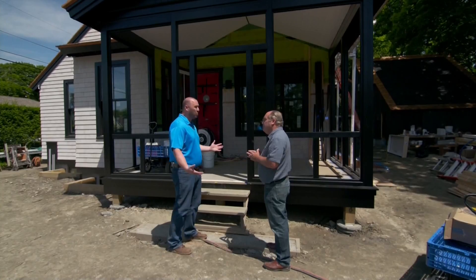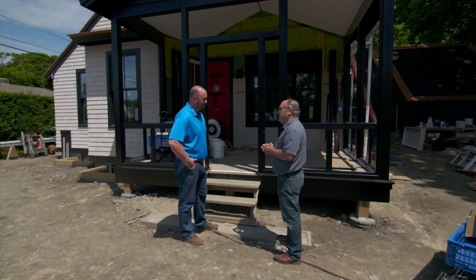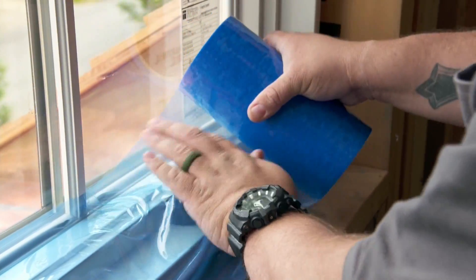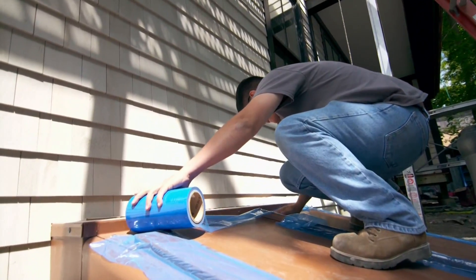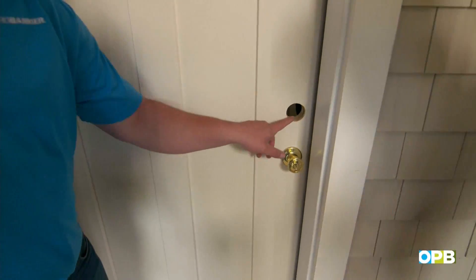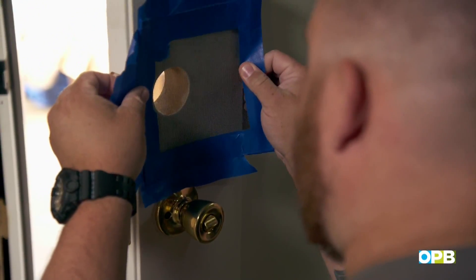What's the worst? I've seen them as high as in the 20s. So 3.8 — what's that equivalent to? That'd be equivalent to probably this window being open about 5 inches or so under pressure. That's a lot of heat leaving out. So what's the prep? The prep process will actually tape off the windows so the sealant doesn't seal them. You've got to seal every single opening, anything that will lead to outside that will eventually be closed off. We're going to use this hole where the deadbolt will eventually be to simulate an air leak, put this mesh here, and actually be able to see the technology seal it.